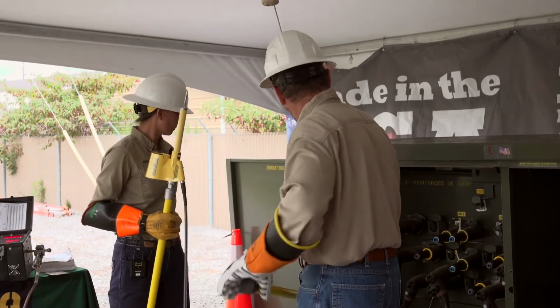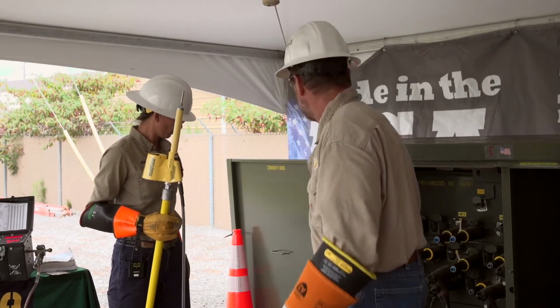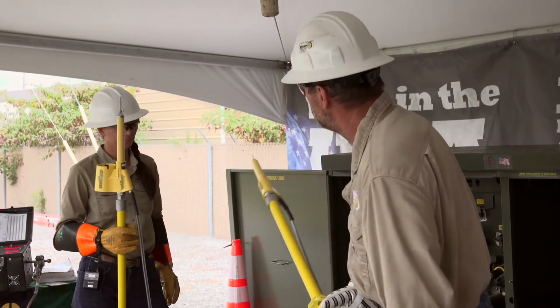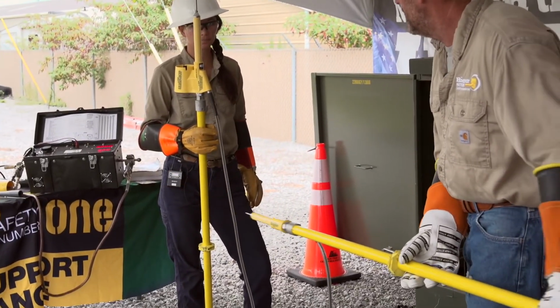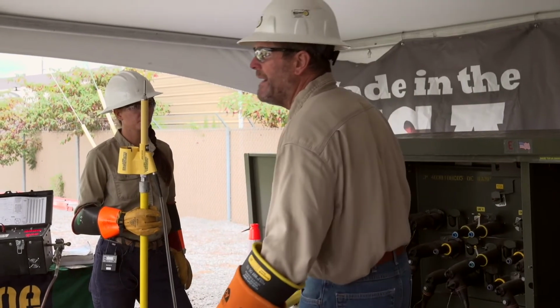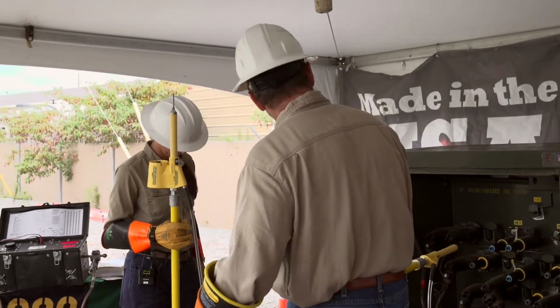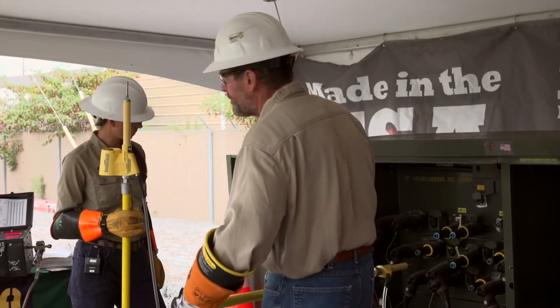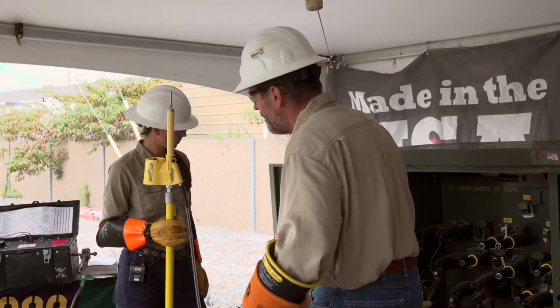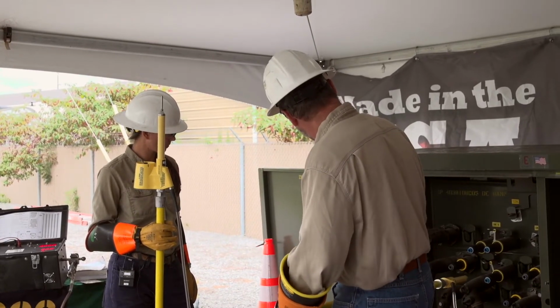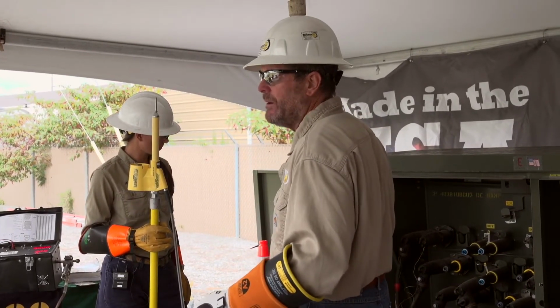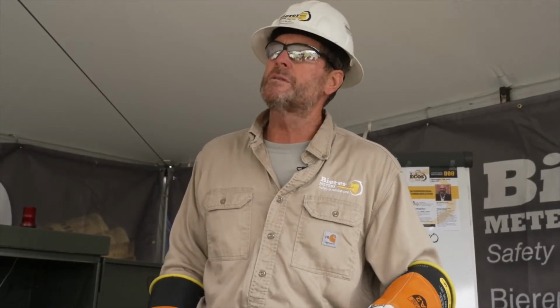Now, one thing you don't ever want to do, remember we talked about proper accessories. See that straight probe on the end of that cone tip? We get this call once in a while. Folks have a probe tip on their tool and they'll go to that hot bushing and put the probe tip inside where that interface is supposed to go from the elbow into that hole. And they call us and say, oh, we had an arc flash. It's like, what the heck, man? That is improper work method right there, buddy. So use a bushing adapter. Some folks didn't realize we had bushing adapters. We do. So use them.